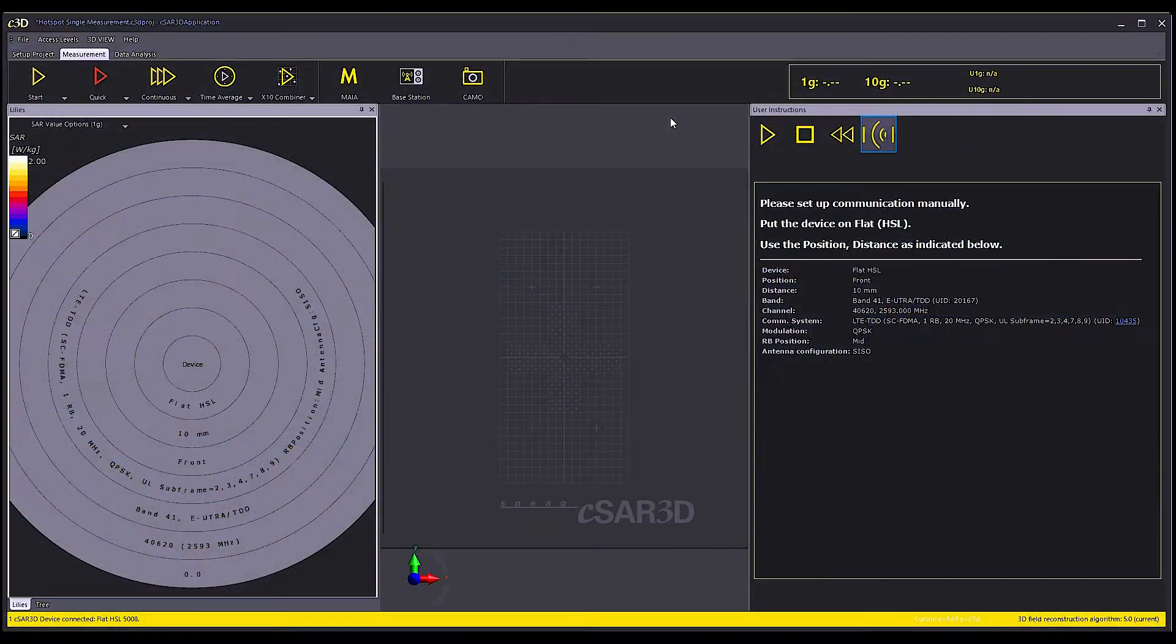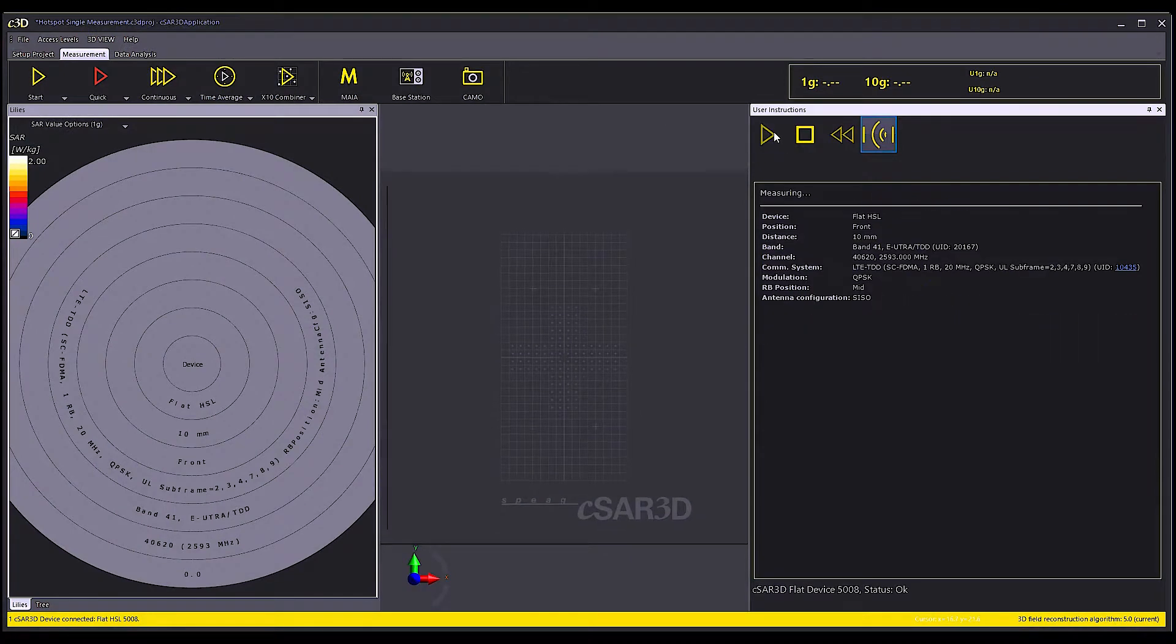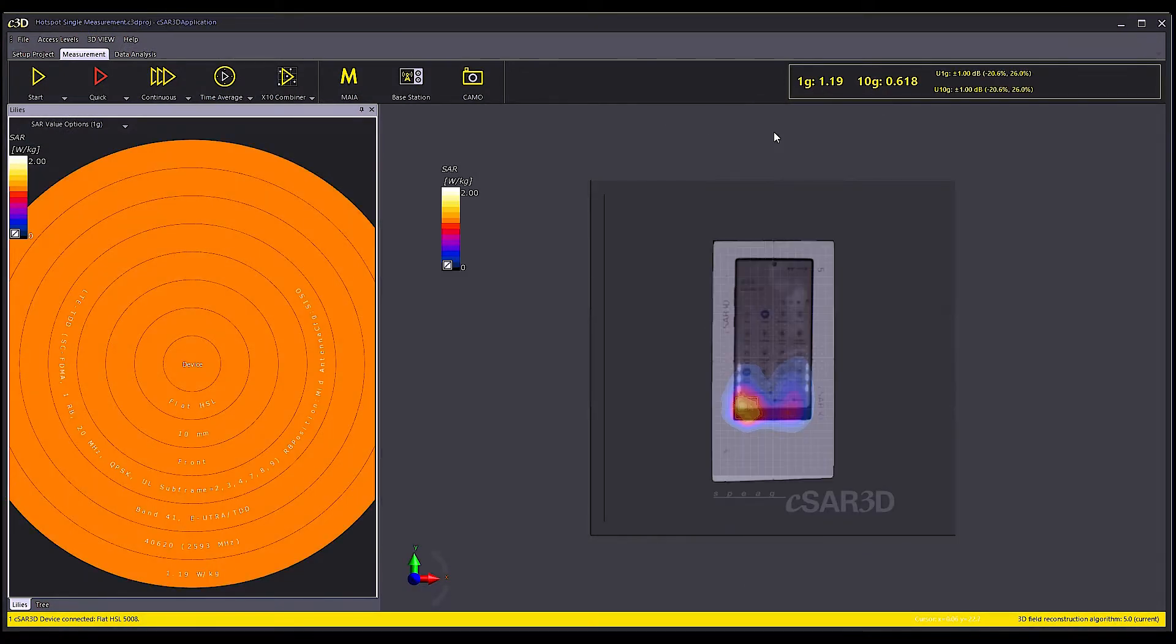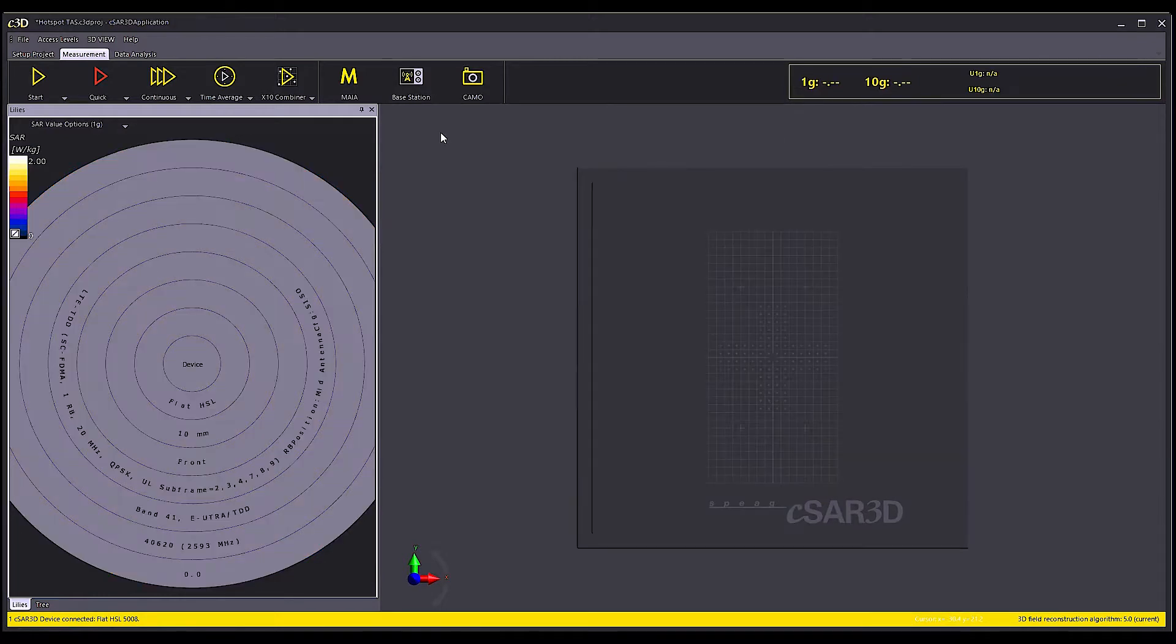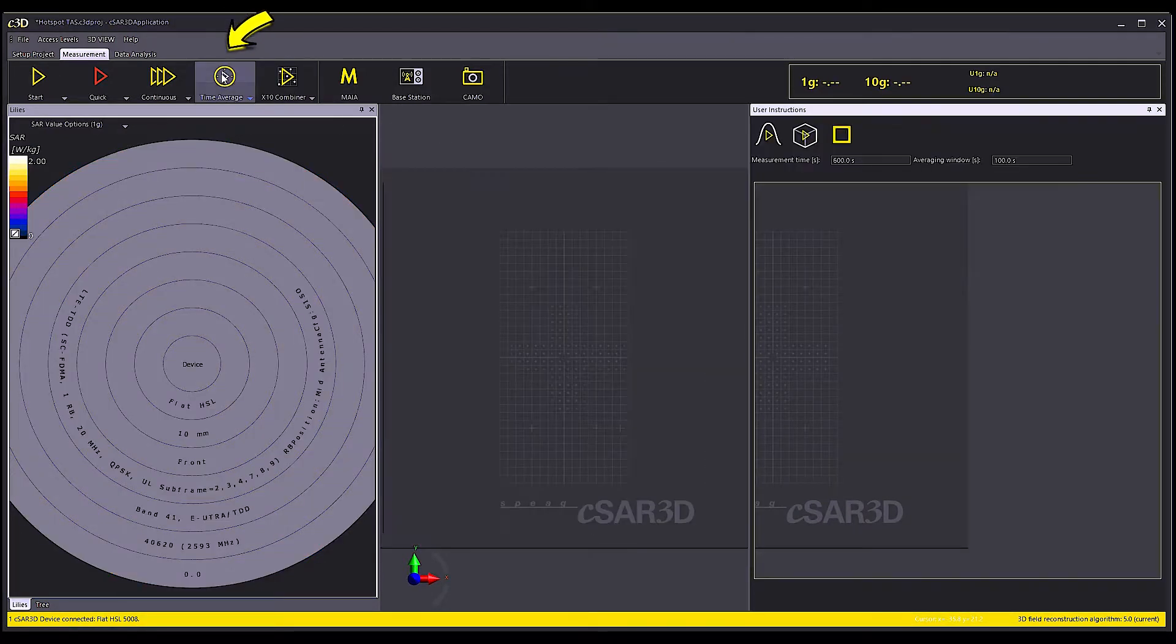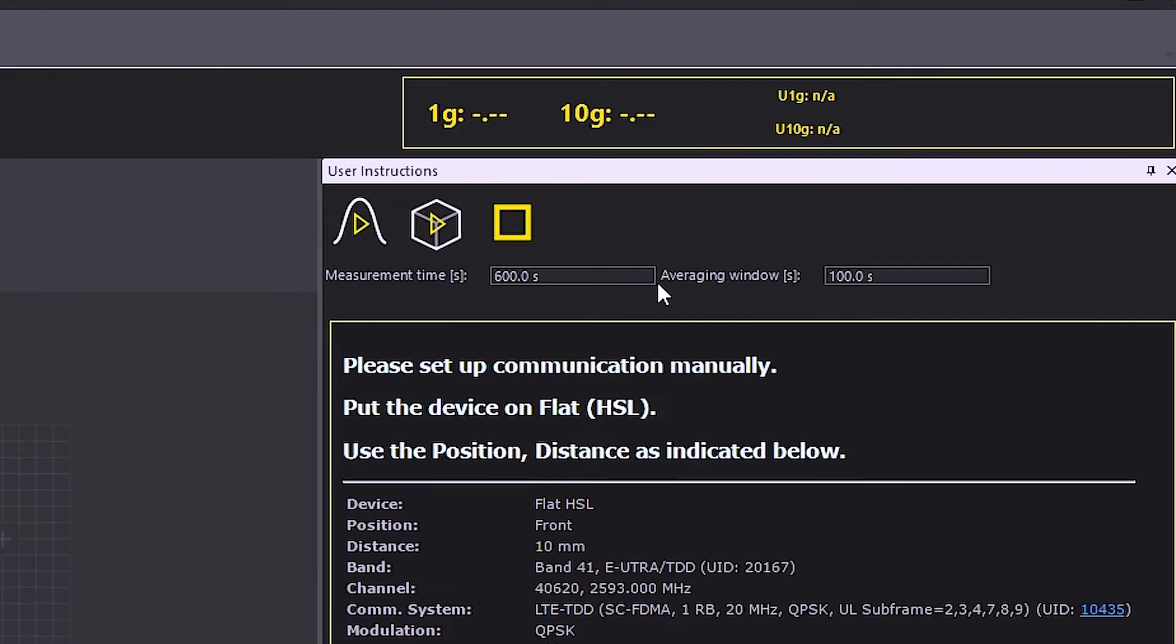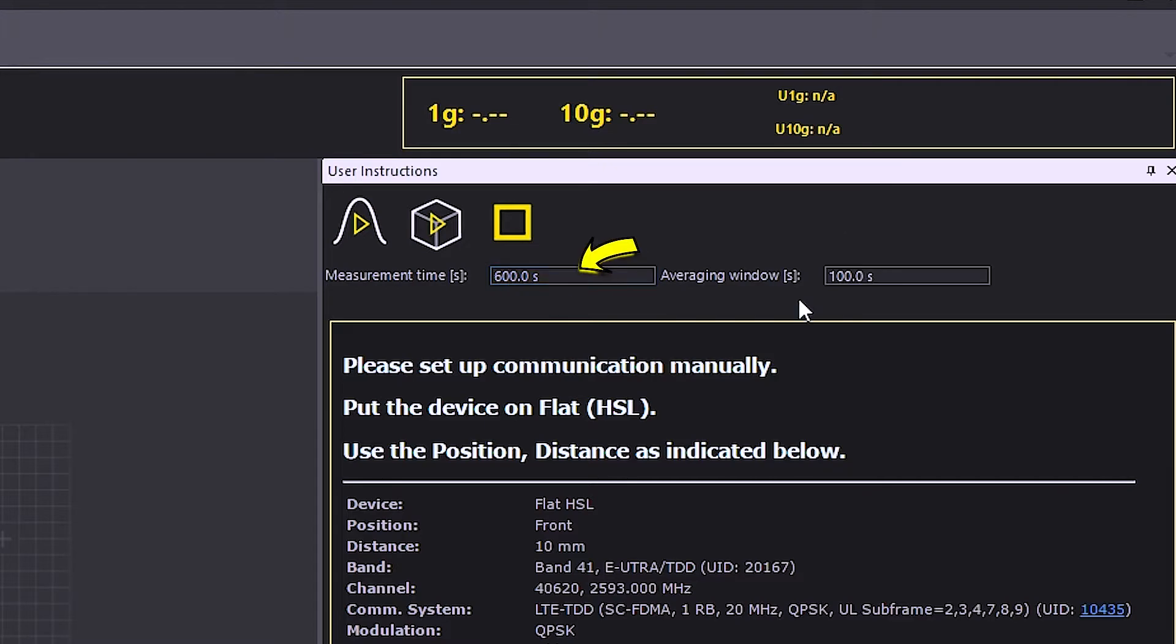You can actually already notice in this step how much faster the response time is. Next, I start the TAS evaluator and set the averaging parameters. In this example, I set the averaging time to 100 seconds and the measurement duration to 600 seconds.